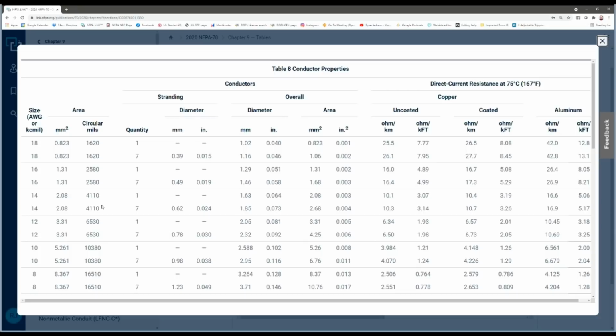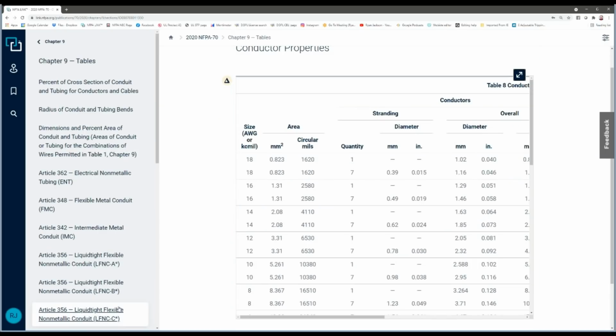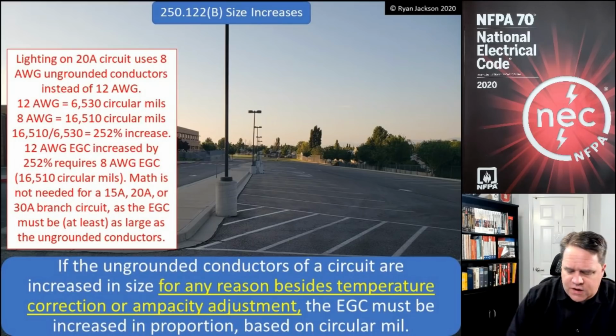I increased the size of the ungrounded conductors from 6,530 circular mils to 8 gauge, which is 16,510. And you can see that that's a pretty substantial increase. We need to do a little bit of math and figure out how to get there. So let's bring back up the PowerPoint. 6,530 circular mils and 16,510 circular mils. So if I do the math, that is a 252% increase. So 16,510 divided by 6,530 is 252%.